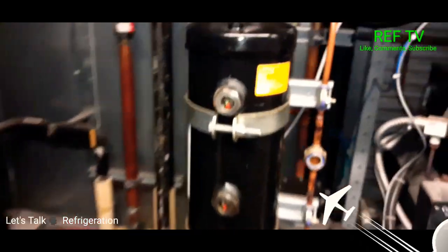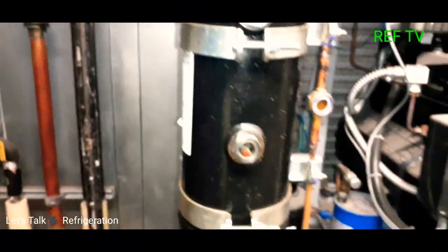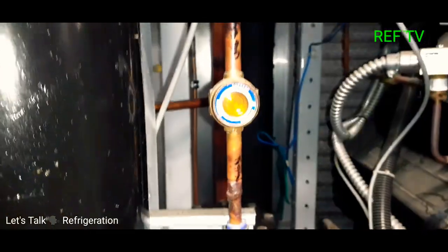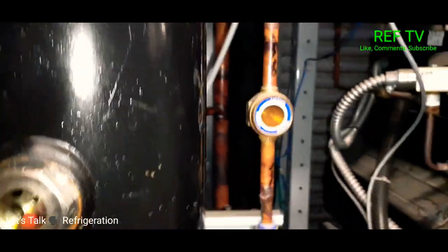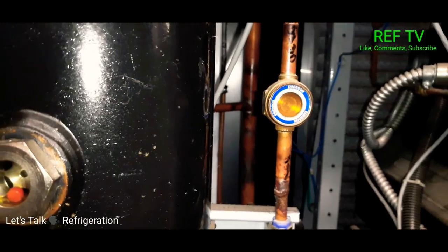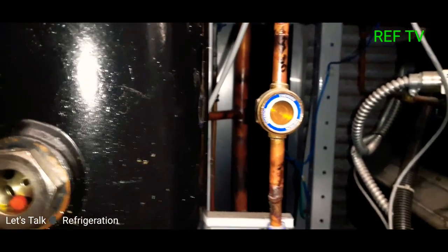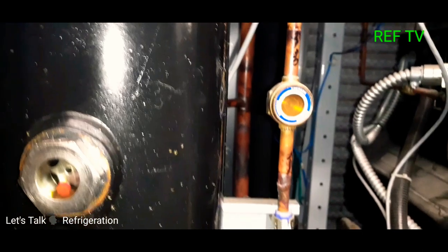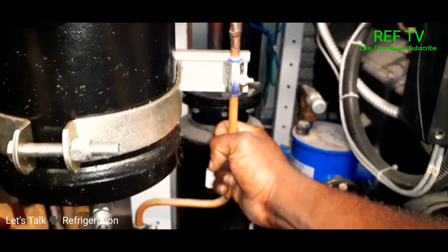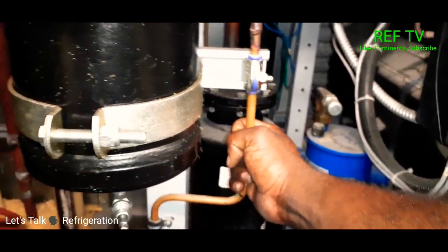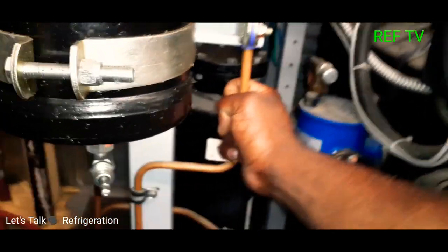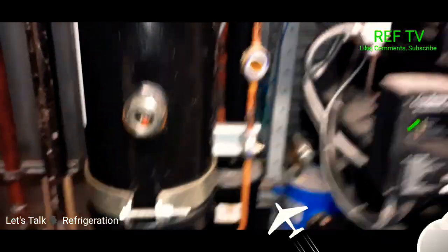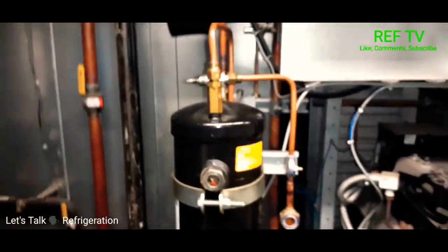Let's just check out our oil reservoir. Zero bowls of oil. Also, let's check our sight glass. So that's the next thing I like to check. Normally you should see bubbles in this sight glass. Also, if you touch this line it should be hot, and right now it's not hot, so it kind of tells me that our oil separator down there, the float at the bottom, is not open. Basically, I'm gonna check my oil reservoir. Also, I'm gonna check my net oil pressure at my oil pump.